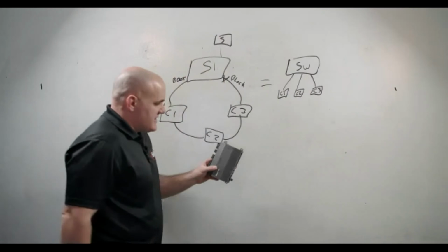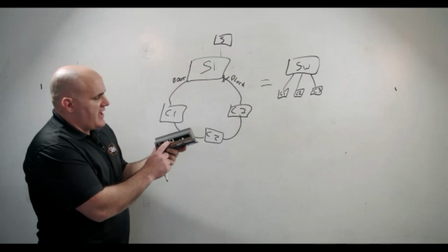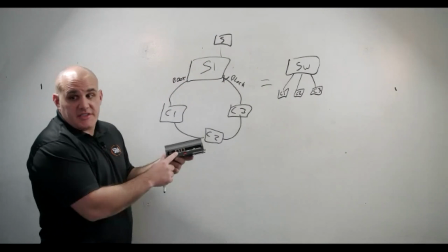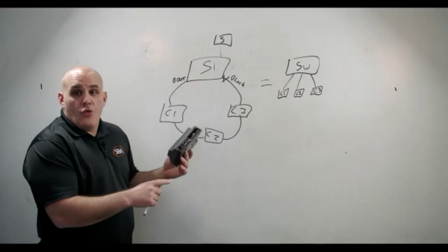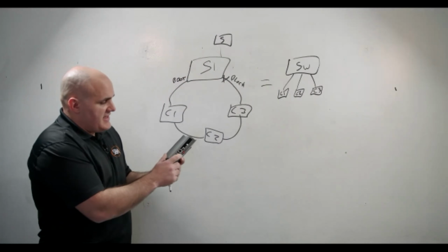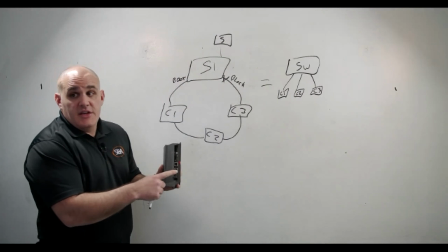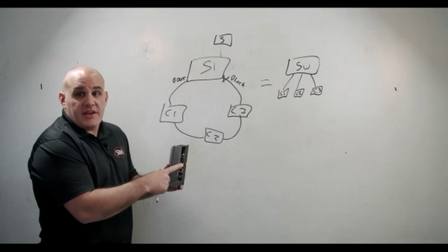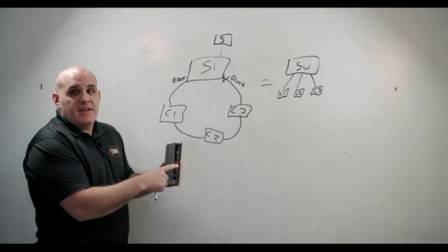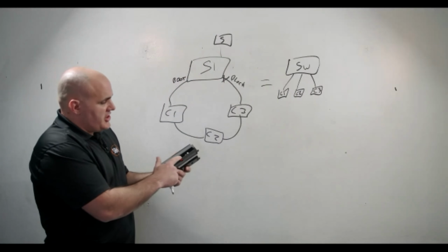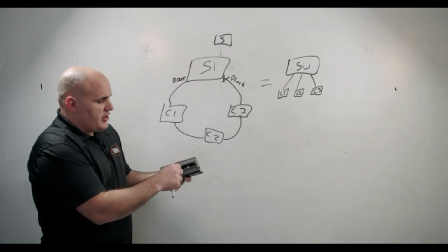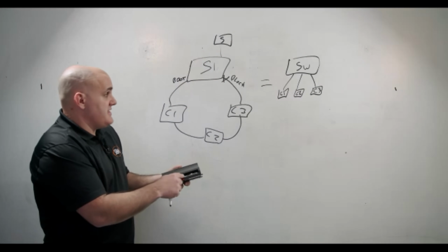All right. So this is Edge 10. It's actually a Cypher 10, but you can see you've got a primary and a secondary, so you can do ring architecture here. Now, what's going on right here is that these are not electrically isolated. So if you lose the connection, if you lose electrical power to this, then you're going to lose the network interface card that's inside of this.